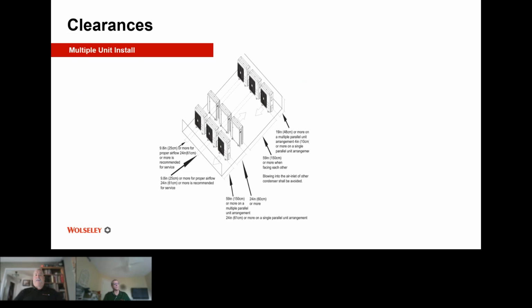Number one, the discharge side, we want to keep at least 59 inches or 5 feet away from the facing of the other unit across from it. What I mean by that is, if you are doing a cooling cycle and the hot air is being discharged from, let's say, the middle row unit, and it's pointing to the third row on the north there, we don't want that heat to inadvertently influence the temperature sensors that are in that unit. So we want to try and maintain minimum clearances when we're doing multiple units.